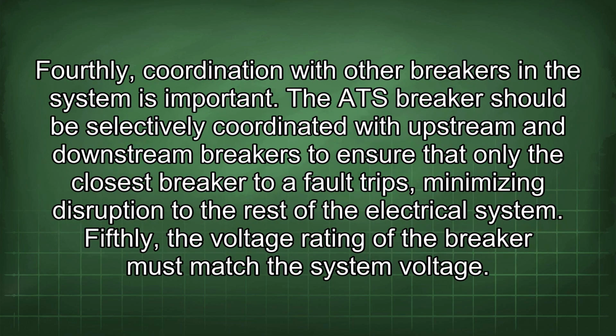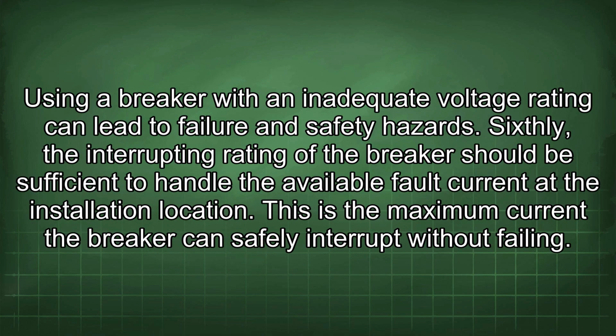Fourthly, coordination with other breakers in the system is important. The ATS breaker should be selectively coordinated with upstream and downstream breakers to ensure that only the closest breaker to the fault trips, minimizing disruption to the rest of the electrical system. Fifthly, the voltage rating of the breaker must match the system voltage. Using a breaker with an inadequate voltage rating can lead to failure and safety hazards.